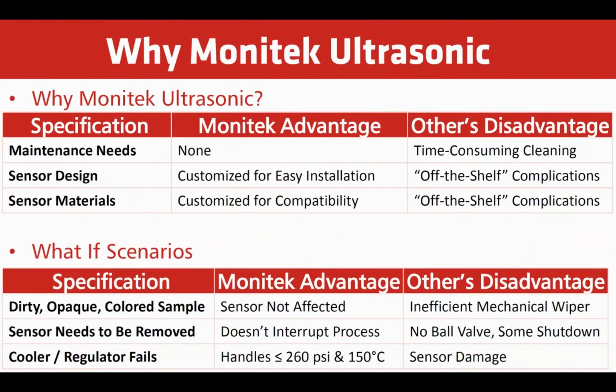So why Monitek Ultrasonic? No maintenance needs. There are no lamps to change. There are no windows to clean. It just sits out there and runs. Sensor design: obviously we can customize the sensor length or the type of mounting to meet the customer's requirements. Again, with sensor materials, for compatibility with their liquids, we can offer a multitude of materials. So we just need to see that from the application and talking to the customer.